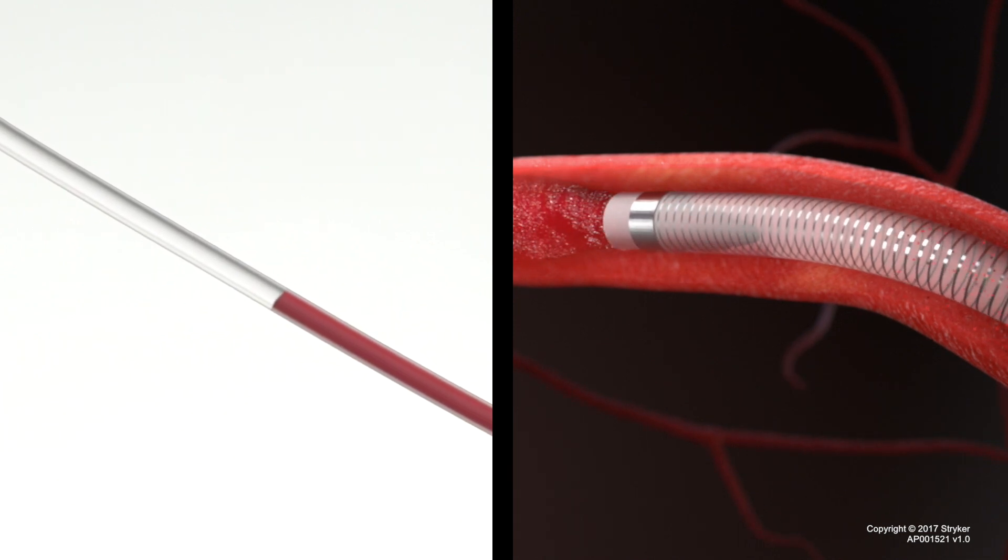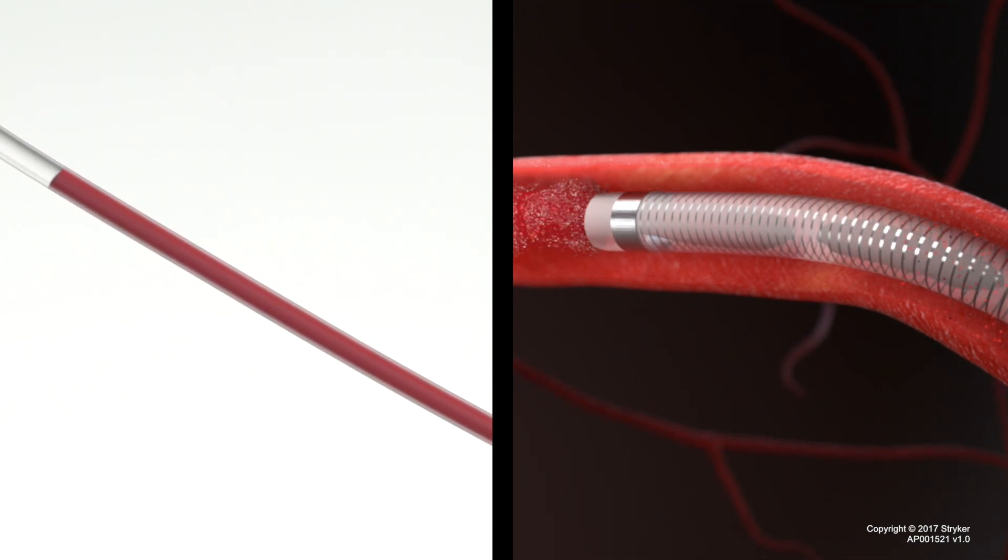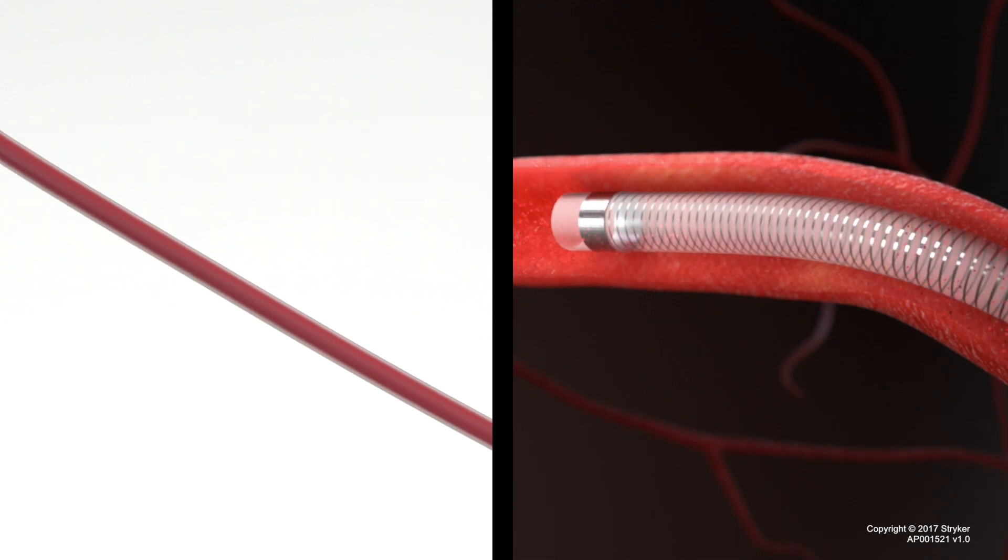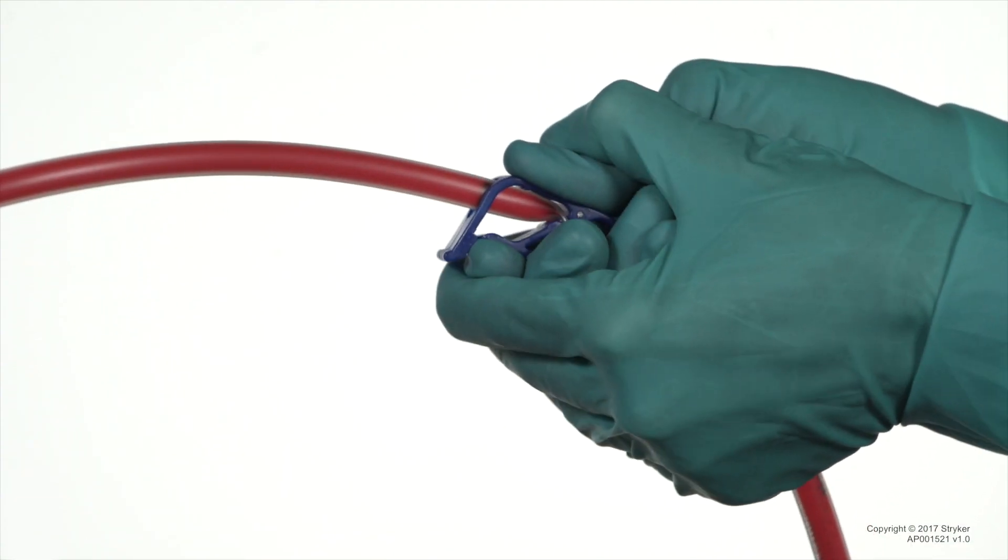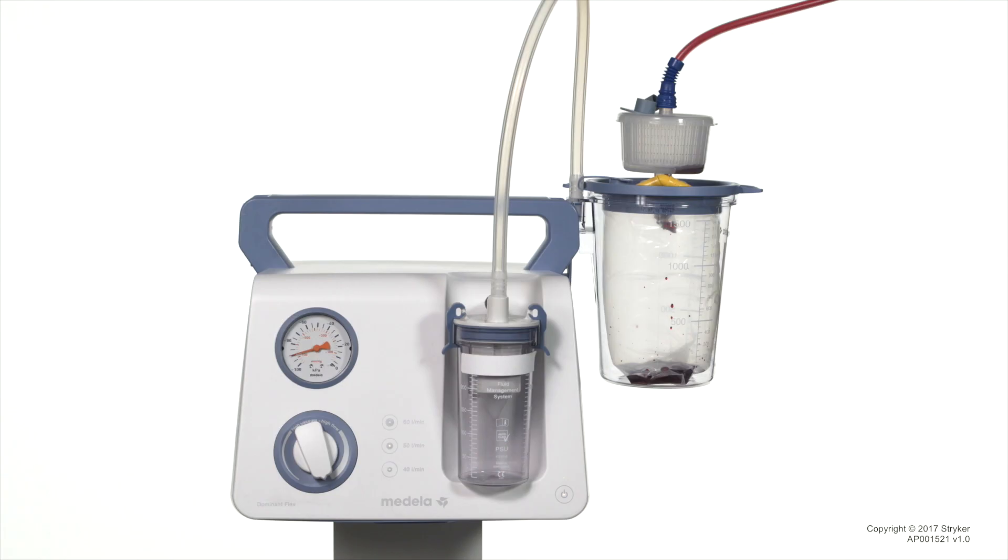If blood stops flowing through the tubing, it may be a sign that the clot is occluding the aspiration catheter. Wait and watch the blood flow in the tubing for signs of clot ingestion. The blue clamp can be used to stop flow at any point during the procedure. The pump can remain on when the tubing clamp is closed.